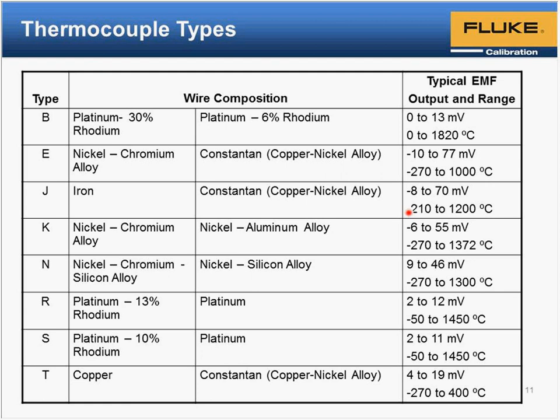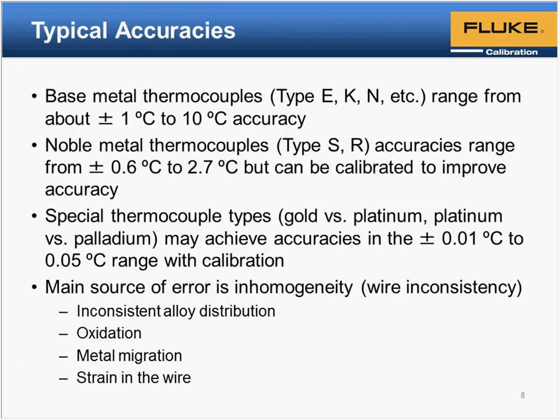They vary from, as a matter of fact, I have those numbers here. Type R: basically, the tightest tolerances are around 0.6 degrees C. Also, at the higher temperatures, they go up as high as 2.7, and that's the special limits of error specification. There are two level specifications for each letter type. Base metal tolerances usually start out at the best they get, 1 degree C, but can quickly go up to as high as 10 degrees C, depending on temperature and the letter type.